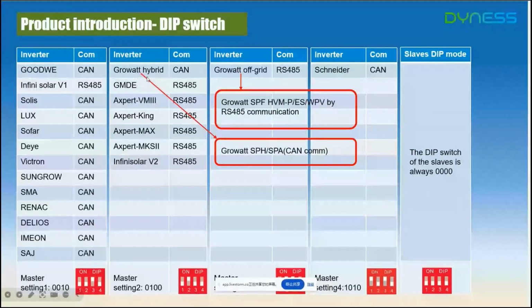You also need to pay attention to another brand's inverter, Growatt, because they have different models: Growatt SPH, SPA, and also Growatt SPF. For Growatt SPH and SPA, they use CAN communication, and the master setting should be 0, 1, 0, 0. But if you use Growatt SPF, they use RS485 communication, and the dip switch should be 0, 1, 1, 0.